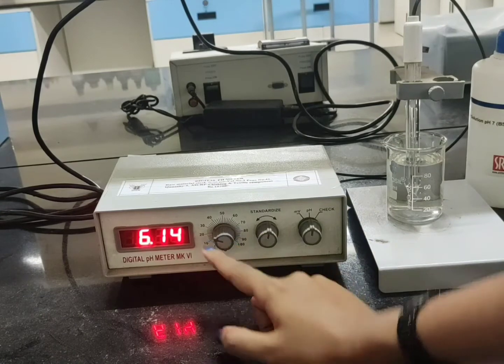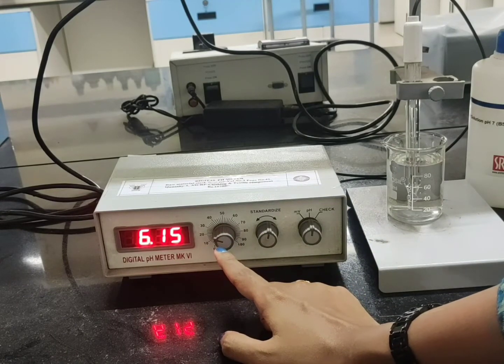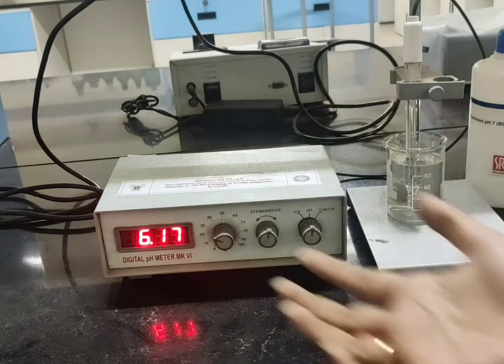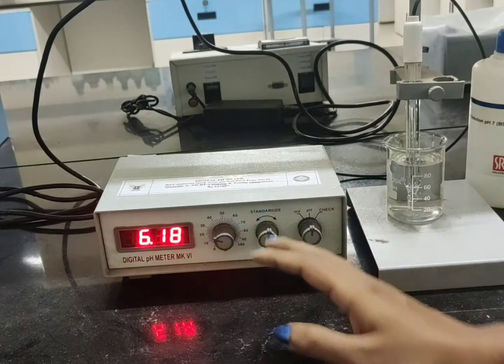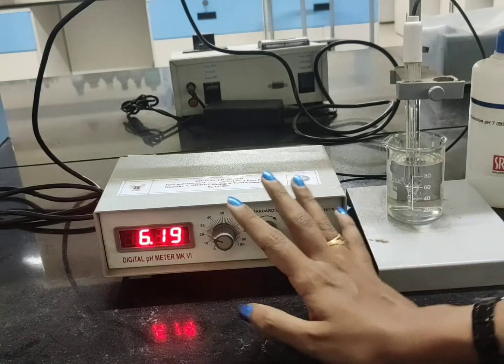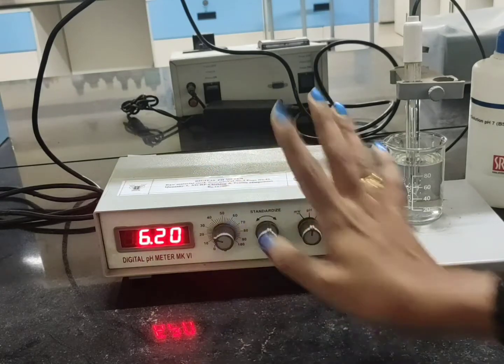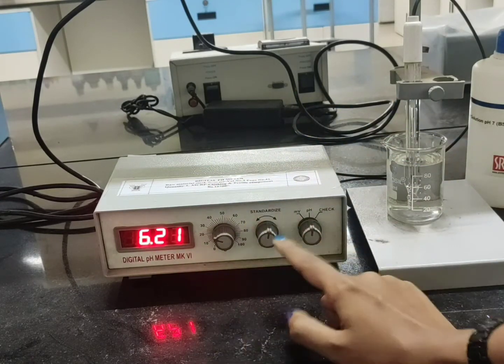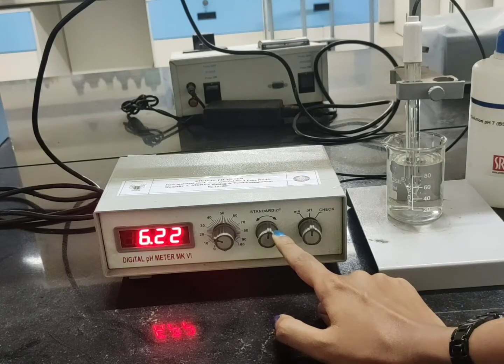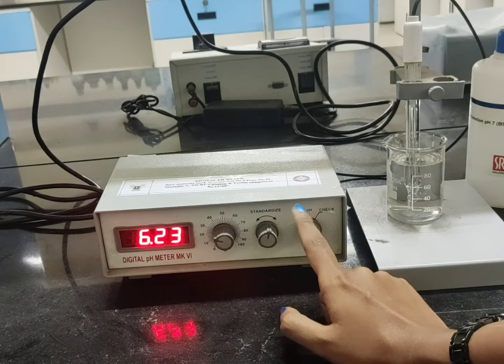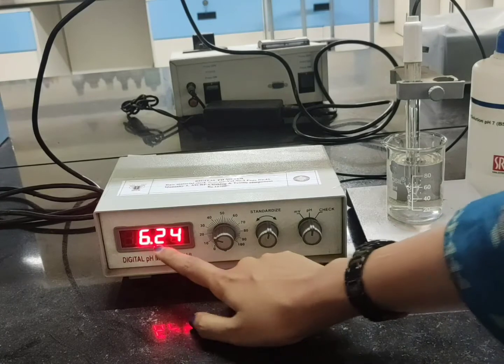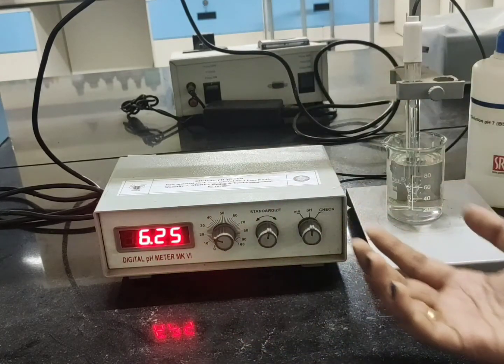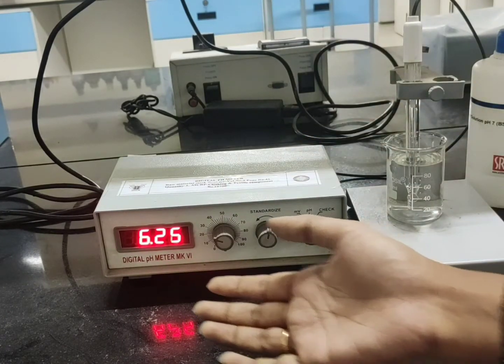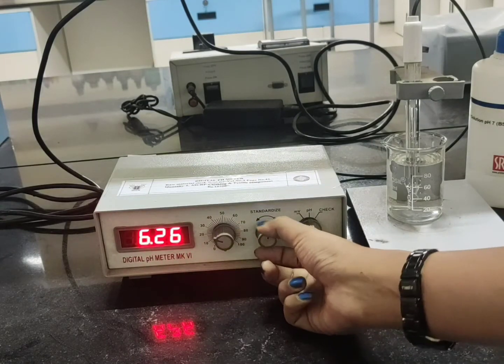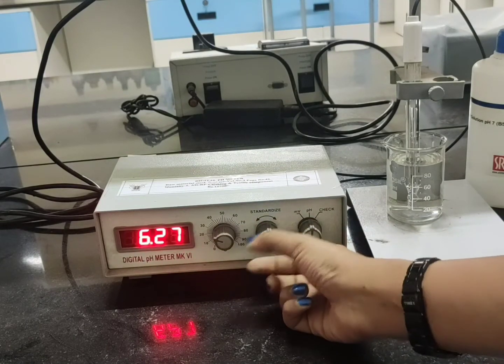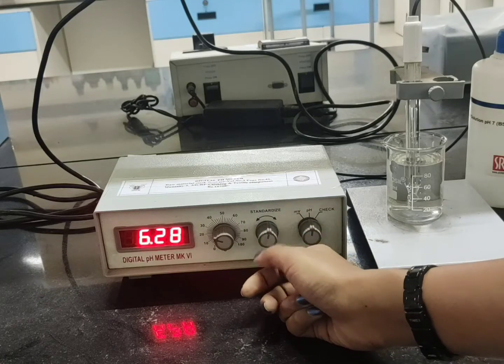So first you see the first knob that has been given is for temperature. So depending on the temperature of the sample that you are reading, you can set the value. Otherwise generally we keep the temperature at 30 and just let it set there. Now the next knob that you can see is for standardize. So that means whenever you are calibrating the instrument, in order to increase the reading that you can see here. So suppose your buffer is 7, but the reading shows 6.5. So by increasing this standardize knob, you can set the buffer or set the pH.